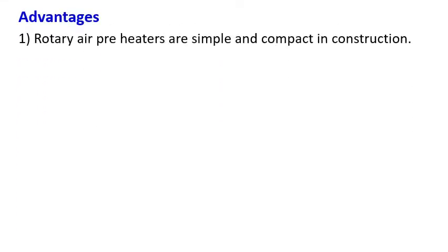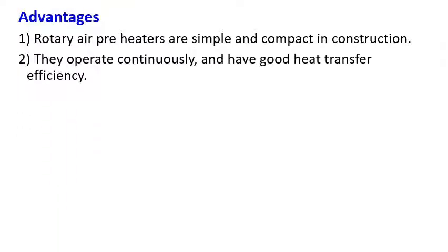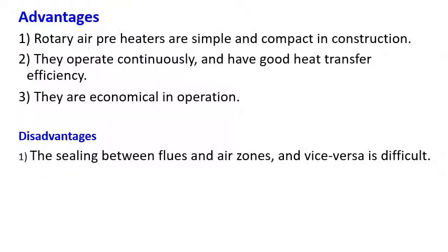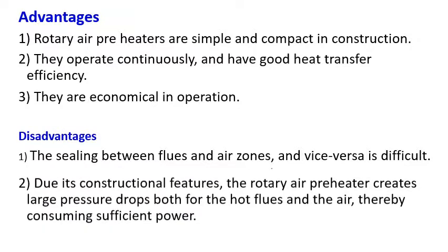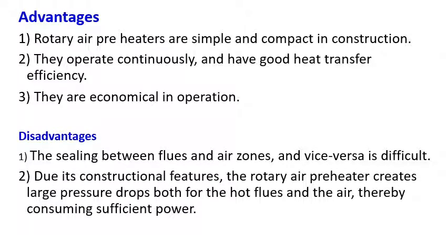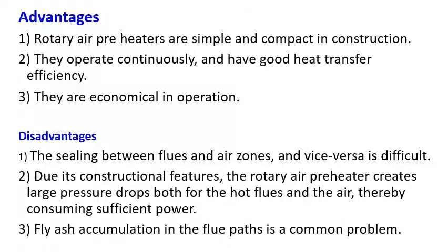The advantages of the rotary air preheater are that it is simple, compact in construction, operates continuously, has good heat transfer efficiency, and is economical in operation. The disadvantages are sealing, as I told you, right? Because of the heat, it breaks down frequently. Due to the constructional feature, the rotary air preheater creates a large pressure drop on both the hot and cold flow, therefore consuming considerable power. Fly ash accumulation in the flue gas path is a common problem. It gets settled on the matrix, which has to be cleaned during annual shutdown, right? That is one more problem.